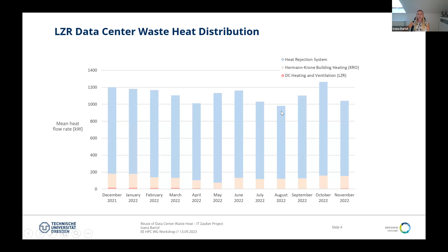To be more exact, out of the 100% of electrical energy that entered the high-performance computer, 11% got dissipated, 78% got rejected through the heat rejection system, and only 11% got reused by the heat recovery system. To evaluate the system's efficiency, we will use these three metrics: power usage effectiveness, energy usage factor, and energy reusage effectiveness.